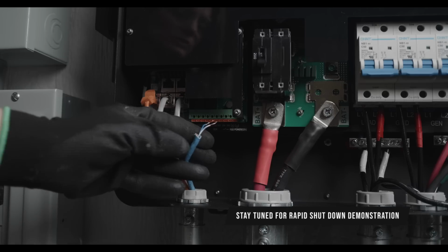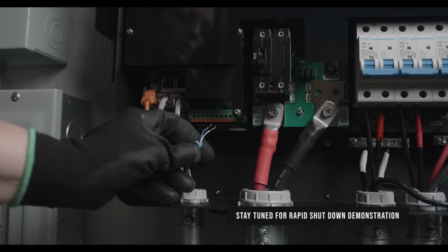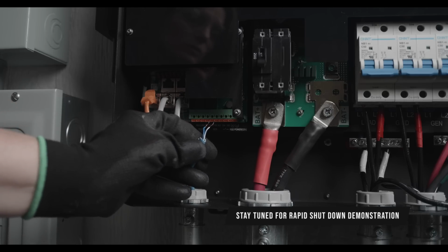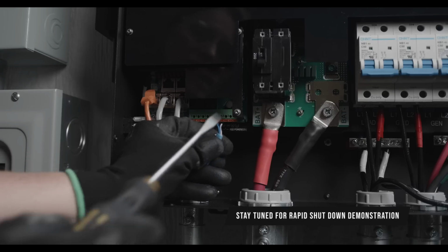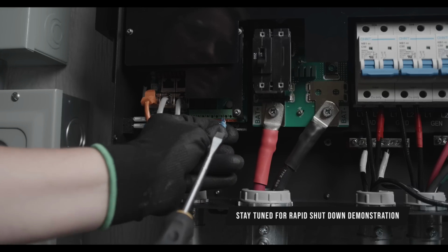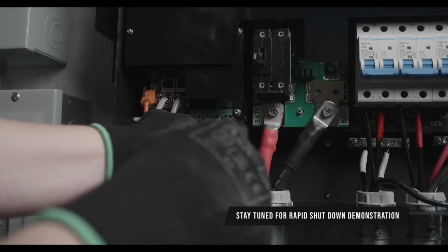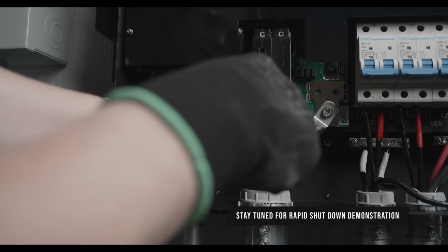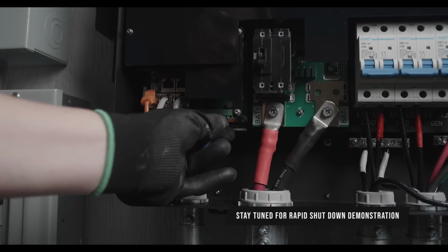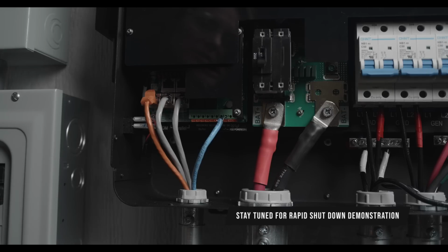This inverter is also capable of rapid shutdown. We can take an external initiator with normally closed contacts, and we can wire it up here to our SW contacts. Prepare it for rapid shutdown when the button is hit.